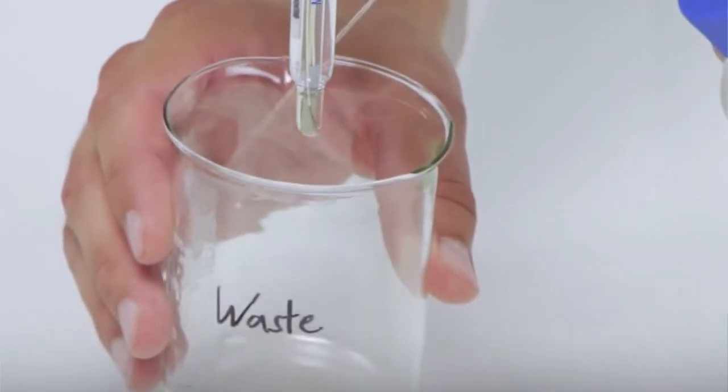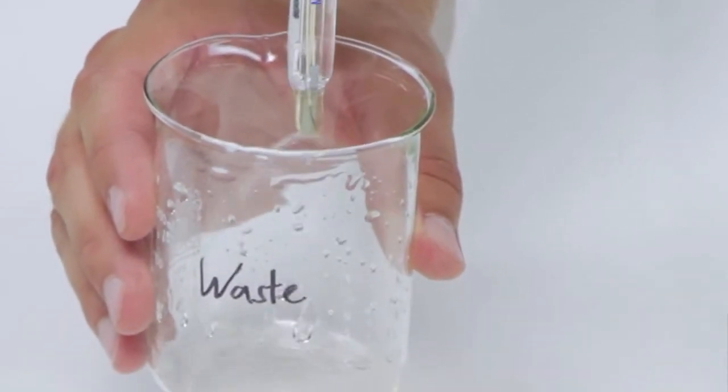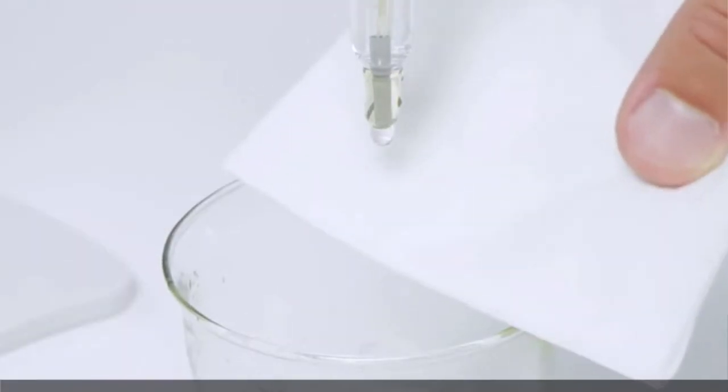Rinse the tip with deionized water from the wash bottle. And then, dab the glass gently with a clean sheet of Kimwipe. Place the tip inside the beaker with the deionized water. Your pH meter is now ready to use.